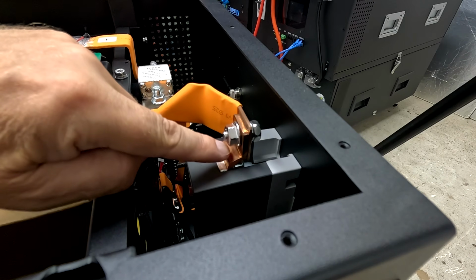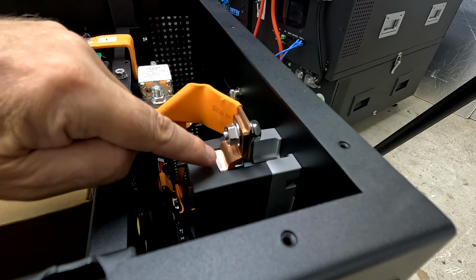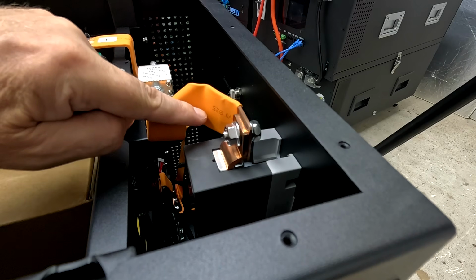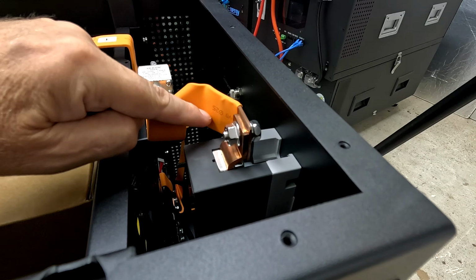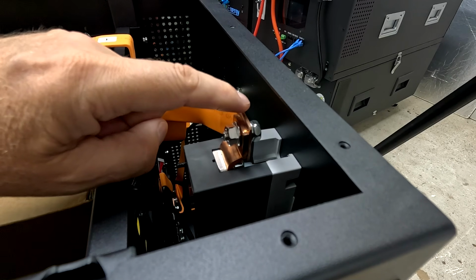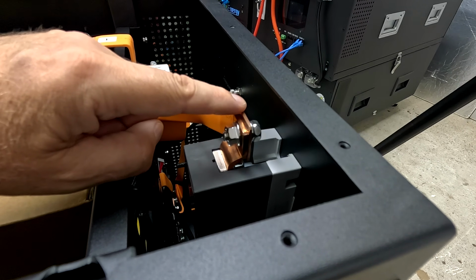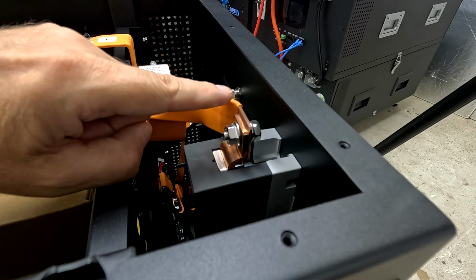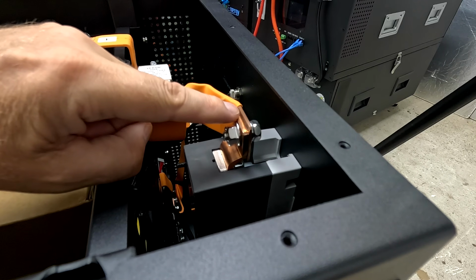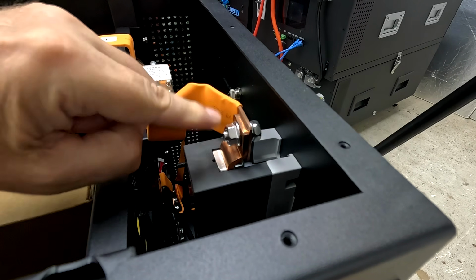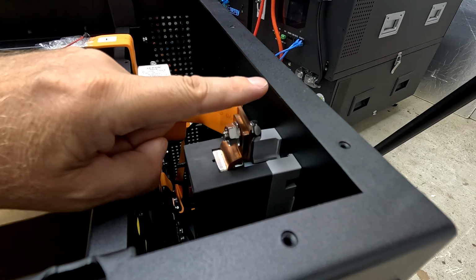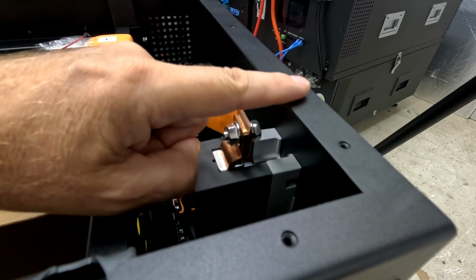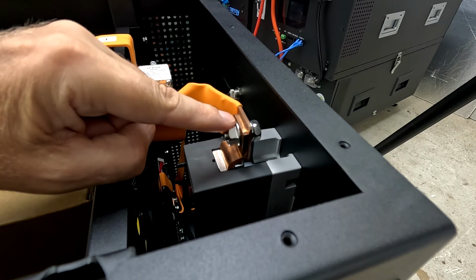I would have probably designed a copper link coming from the circuit breaker and going this way, at a 90-degree angle, made as wide as the flexible bus bar on the outside. Same width. This would have two advantages: it gives us the full contact area between the flexible bus bar and the link, and we also don't have this close proximity anymore between the metal lid and this exposed connection point.